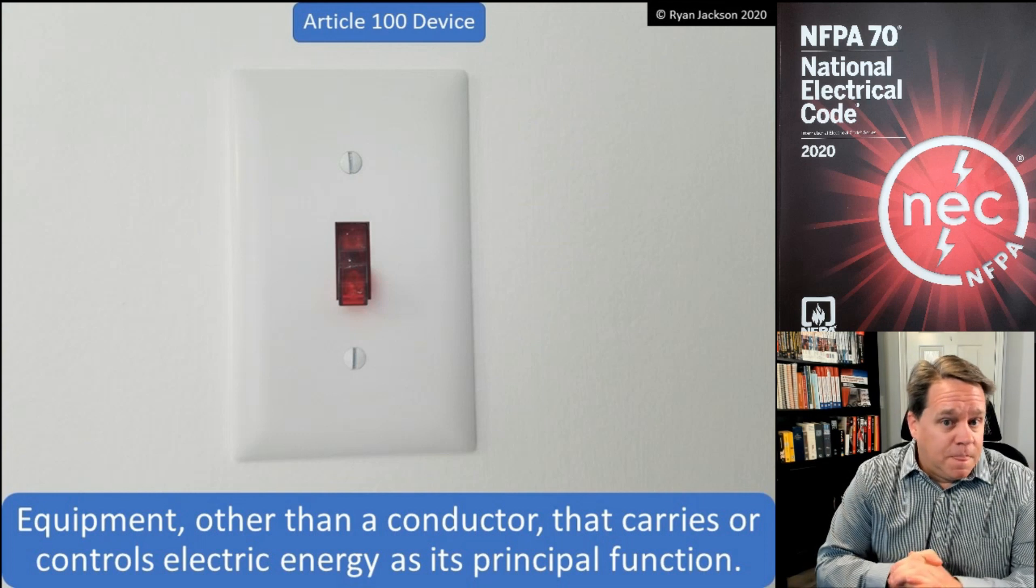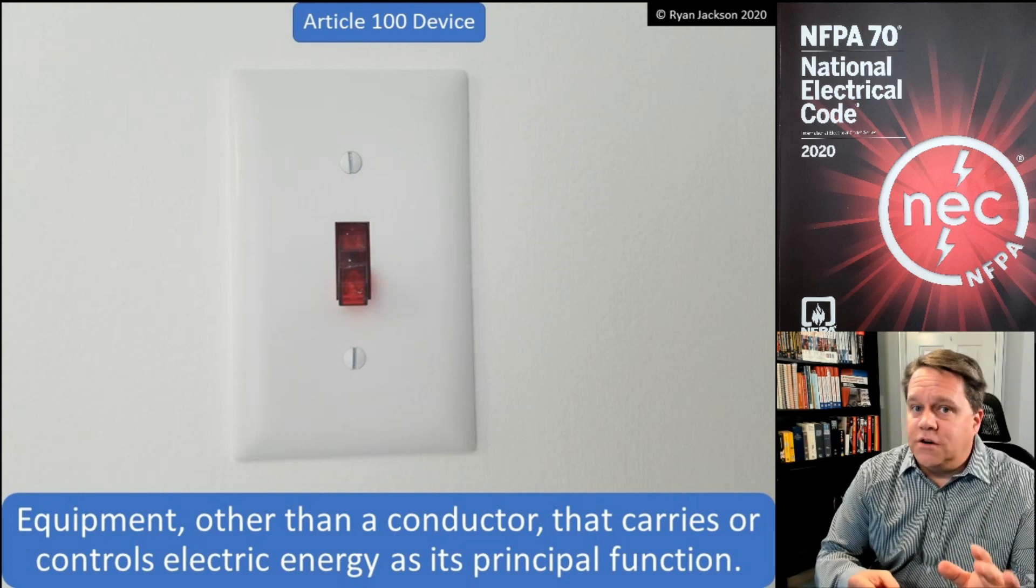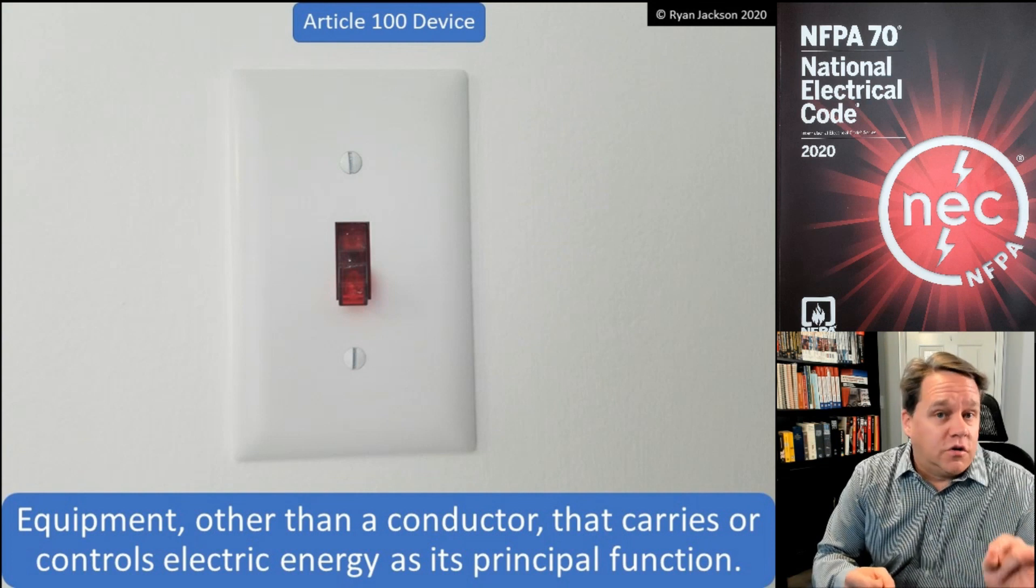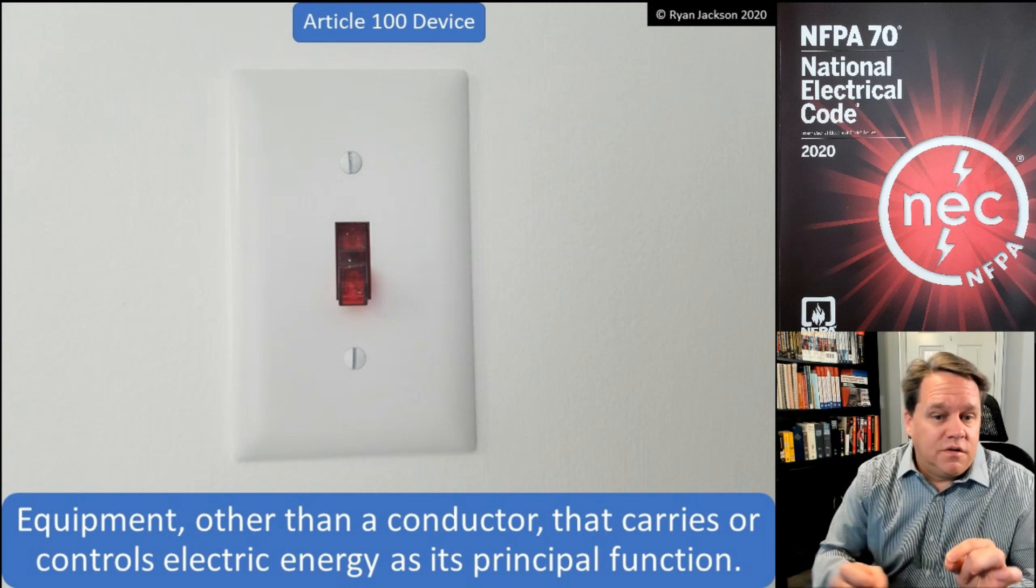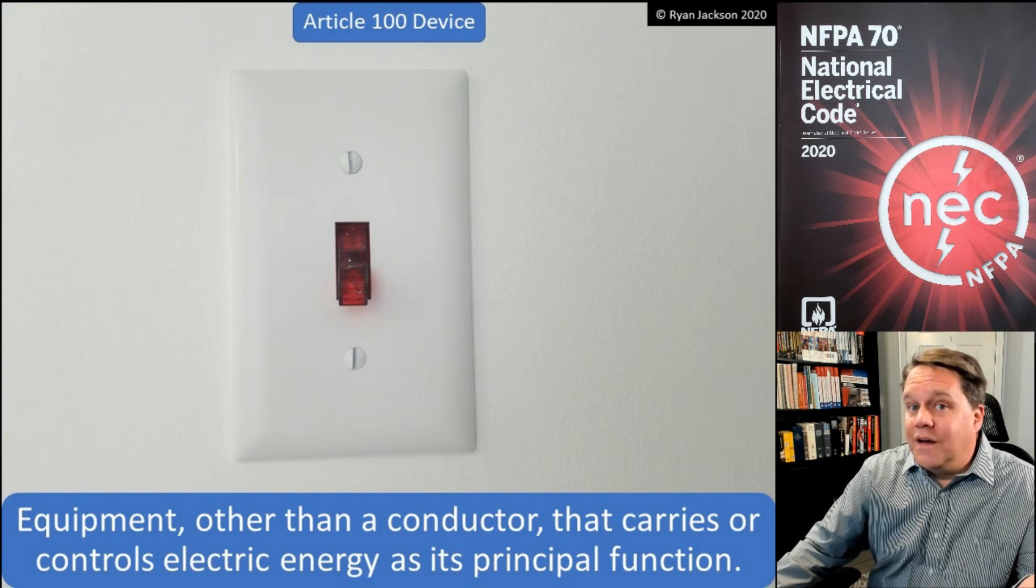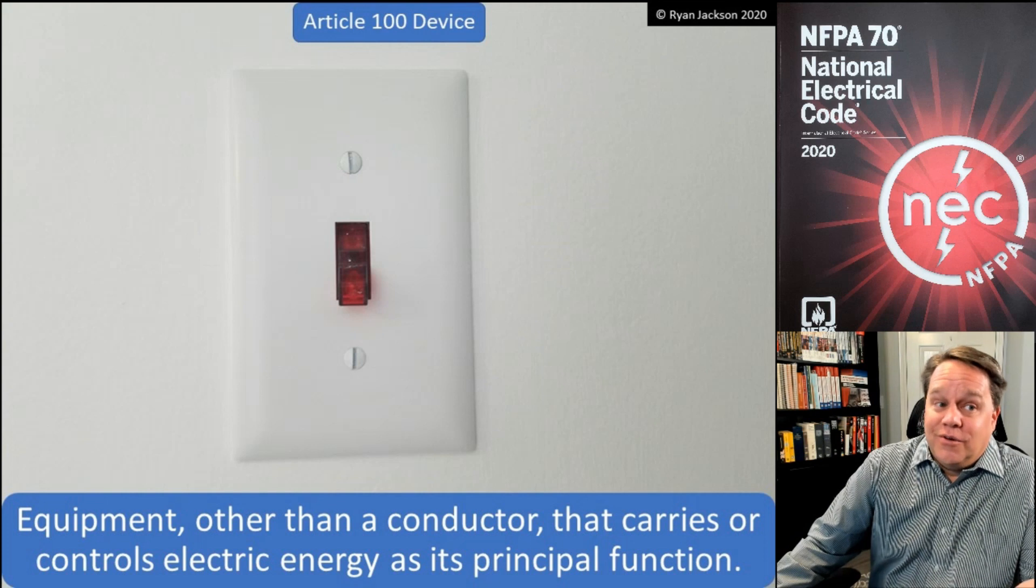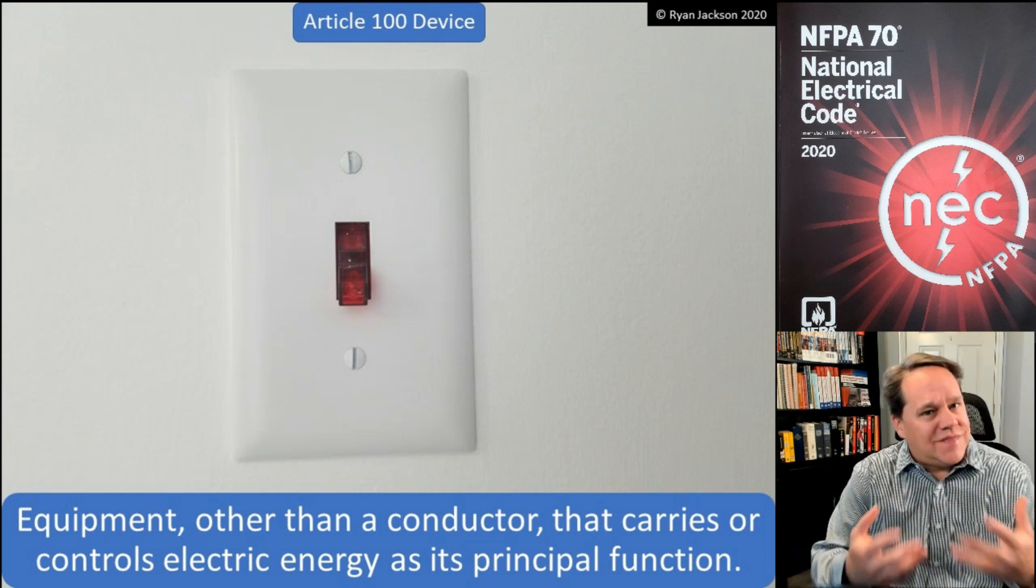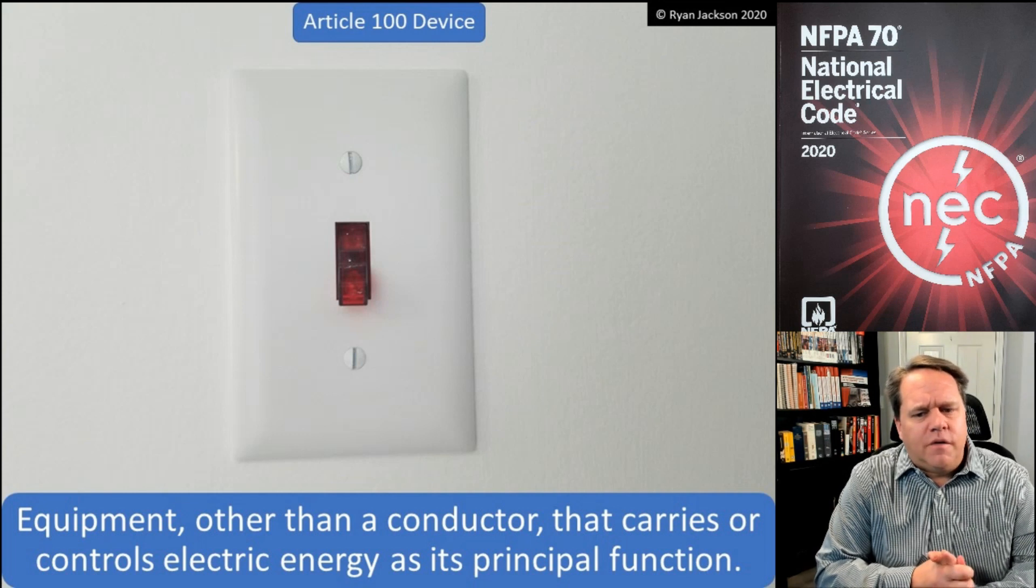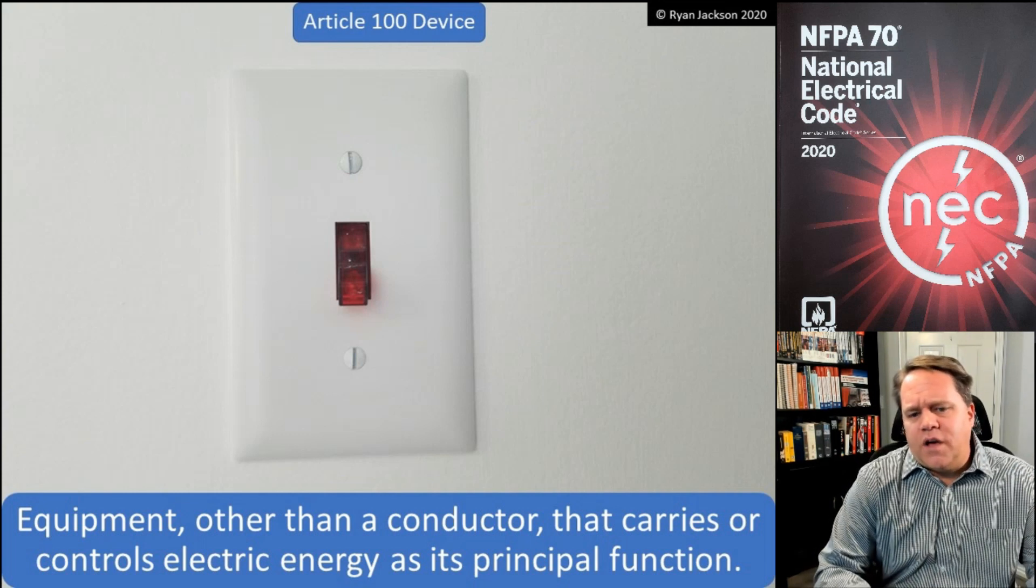We have an illuminated switch. Now again, the old definition said it controls or carries or controls energy but does not utilize it. Well this does utilize electric energy, maybe like one watt, but it is utilizing energy. So with that said, they changed the definition several code cycles back to clarify that it carries or controls energy as its principal function.